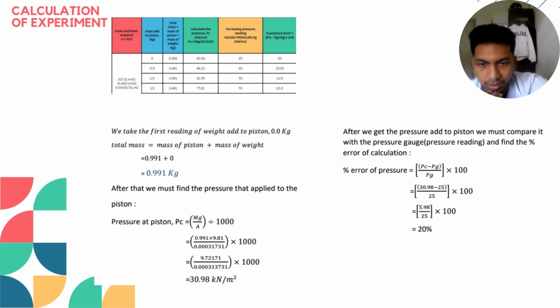So after we get the pressure at the piston, the PC, we have to compare the pressure at the piston with the pressure gauge. After that, we have to calculate the error of calculation. For this error of calculation, we have PC minus Pg. The PC is the pressure at the piston, and Pg is the pressure gauge, that is the pressure that is read in the gauge. After that, we have to divide it by the pressure gauge and multiply by 100. So after we do this calculation, we can get the error percentage for the first reading, which is 20%.